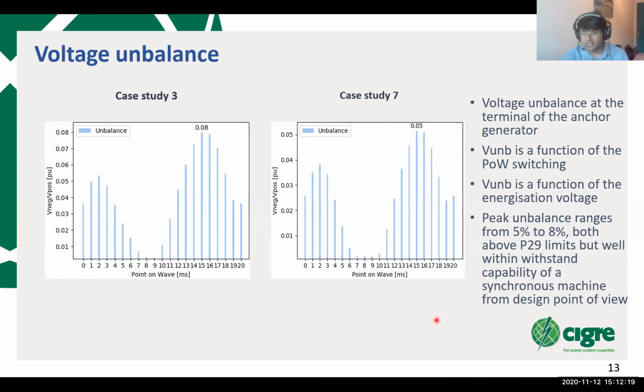So the key takeaways from here would be that voltage unbalance is a function of point-on-wave switching and energization voltage, both of them. And we can reduce the peak unbalance if we adopt any of these intervention techniques. In both cases, the peak unbalance is slightly more than the P29 limit. So one option would be that we can tweak the negative phase sequence protection of the generator to adapt it during the duration of the restoration, so that due to this unbalance, the generator doesn't trip. The 5 to 8% unbalance observed here is not a problem from the generator's machine design perspective. The synchronous machine can withstand this unbalance, but it's the protection setting which will cause it to trip. So we can update that one.